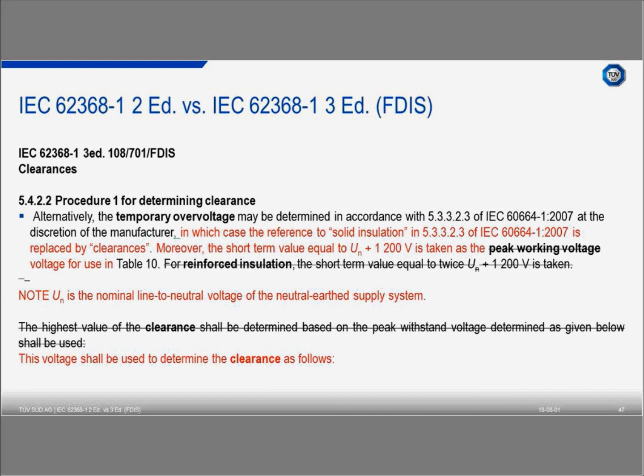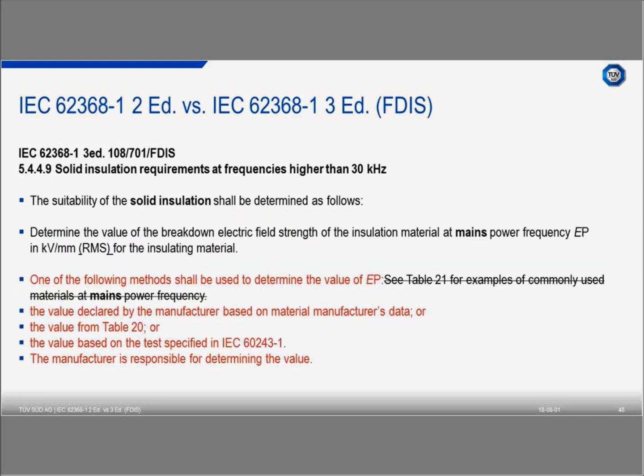Okay, this is a clarification. For the temporary overvoltage, there was a topic that we use 2 times the nominated voltage plus 1200 volt. That was wrong, so there's an update here: we have to use 1 time the nominated voltage plus 1200. So this is a clarification. That was a mistake from transferring this part from 664 to the 62 to 68.